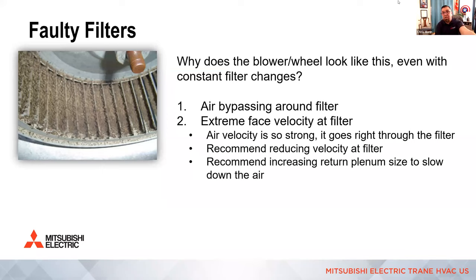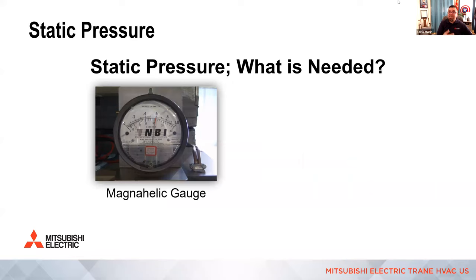And all of the dirt ended up in the blower wheel or the secondary heat exchanger or the coil on a heat pump, right? So these things should be triggers on service. The first thought of most technicians is, they probably replaced this filter before I showed up, right? I'm willing to bet if they measure static pressure or measure velocity, they would be able to tell really easily if that system is within design, if it was designed, right?